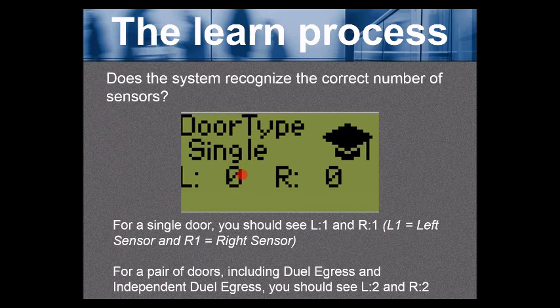In this screenshot, zero, the micro scan hub does not recognize any sensors at all. If this was a single door, you should see L1 and R1 for a left sensor and a right sensor. If it was a pair or dual egress, you would see L2 and R2.